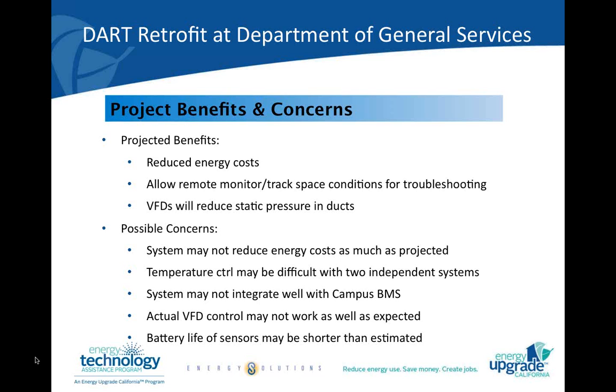Some concerns we have: whether the energy savings will really be what's projected, and whether temperature control is going to work as well as expected. We have these wireless sensors that we will put some settings on, and they may not align with what happens with the pneumatic stats. Somebody can go to a pneumatic stat and change it, and then the wireless sensor would still be thinking it's supposed to be monitoring at different temperatures. So it's going to be interesting to see how that works out.